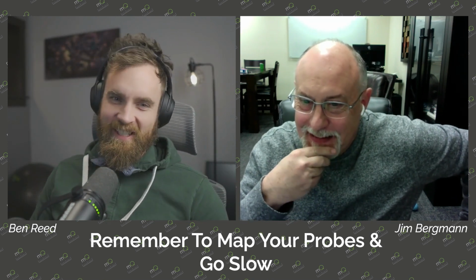One season. Yeah, one season. Awesome. And ductless mini splits, is it the same challenges? It's a lot of the same challenges, except we have a mini split mode for mini splits. It's the same set of challenges with less information, because mini split manufacturers have fewer ports. So we basically have a vapor line only in this case. We have hot gas going out and warm liquid coming back in heating mode, versus cool gas out and back. So things change around a little bit.